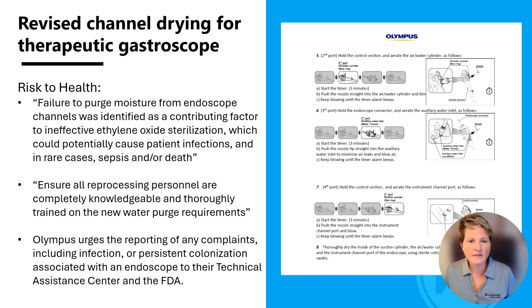So here's what some of the additional messages said in there. It said, as far as being a risk to health, that failure to purge moisture from endoscope channels was identified as a contributing factor to ineffective ethylene oxide sterilization, which could potentially cause patient infections, and in rare cases, sepsis or death. Got to cover everything, right?